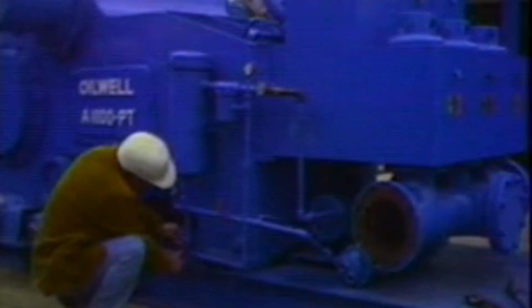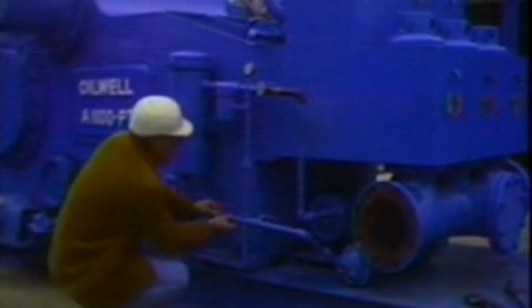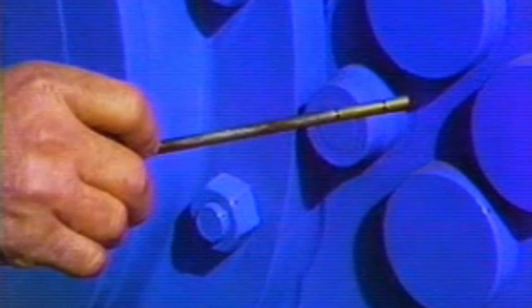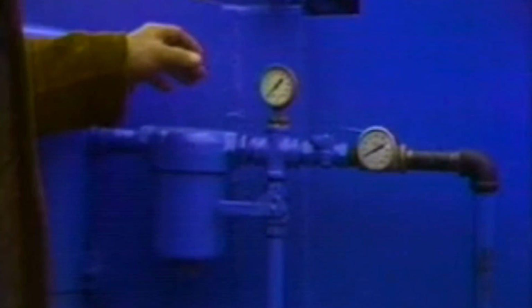Now's a good time to check the extension rod clamps. Make sure they're tight. Loose clamps can cause damage to fluid end parts. And look at the flushing sump strainer in the cradle to be sure that it hasn't scaled over or clogged up. If your pump's diaphragm housing, which holds the rod wiper rings, is equipped with grease fittings, you need to grease it every day. Always keep an eye on the oil pipes for leaks. Okay, your oil level checks out, so start the pump back up. While the pump is operating, look at the oil pressure gauges at the filters.